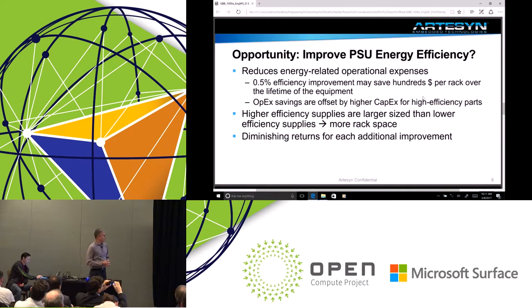As a general rule, if you're pushing the highest power density within a shelf, you're going to have to give some on power efficiency. Likewise, if you're pushing the highest energy efficiency or power efficiency in your PSUs, you're going to have to give some on your density. So this is another area where the operational models come into play. Which is the most important factor? As power suppliers, we can tune this dial in any direction that makes sense, but we're going to have to look at that.